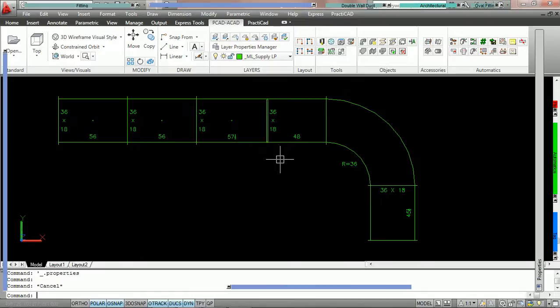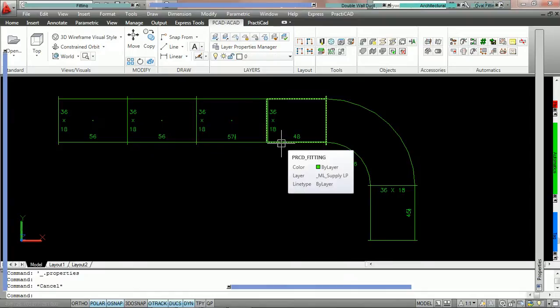So what we have now is a connector in the middle of this duct line that is actually not what the 2-inch water gauge spec table calls for. We've changed it to slip and drive, but Practicad, the spec that it was under, says it should be TDF.